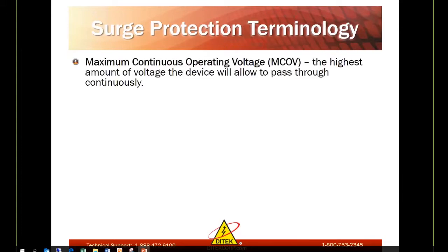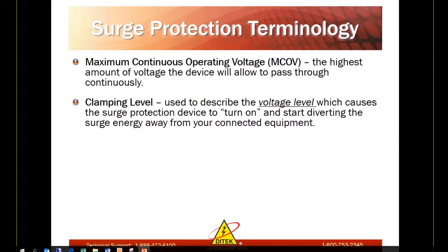Surge protection terminology. Maximum continuous operating voltage, also known as MCOV. This is the highest amount of voltage that our surge protection device will allow to pass through continuously. Clamping voltage is described as the voltage level which causes the surge protection device to turn on and start diverting the surge energy away from the connected equipment to ground.